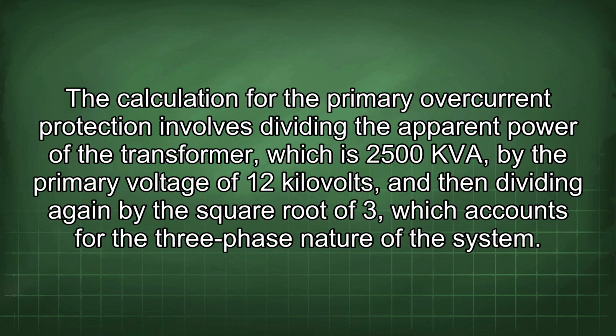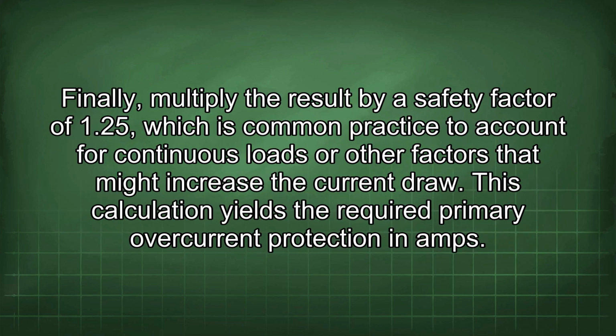The calculation for the primary overcurrent protection involves dividing the apparent power of the transformer, which is 2500 kVA, by the primary voltage of 12 kilovolts, and then dividing again by the square root of 3, which accounts for the 3-phase nature of the system. Finally, multiply the result by a safety factor of 1.25, which is common practice to account for continuous loads or other factors that might increase the current draw. This calculation yields the required primary overcurrent protection in amps.